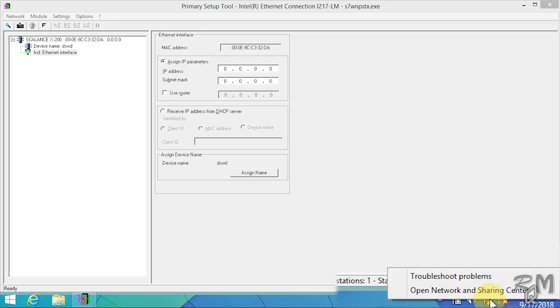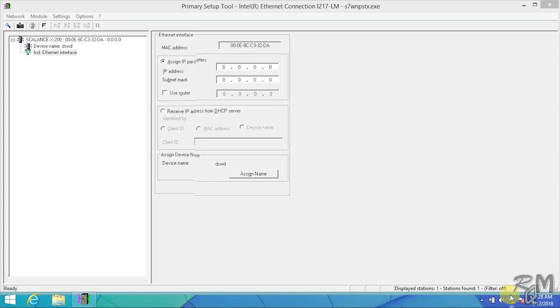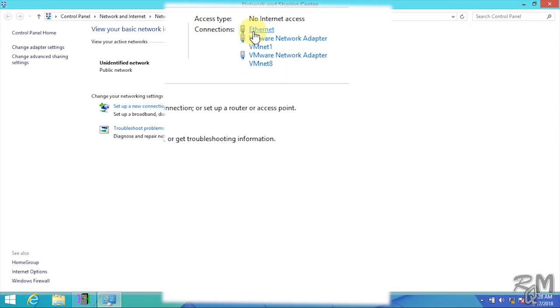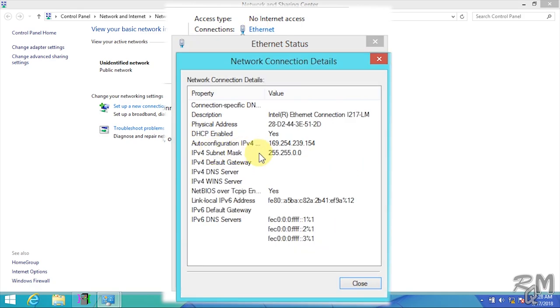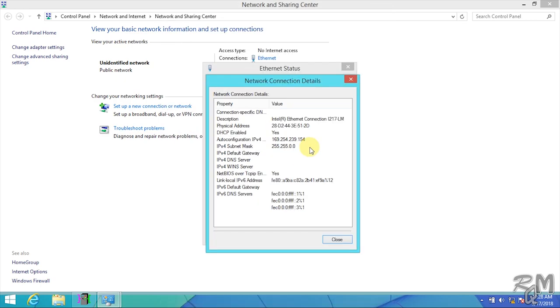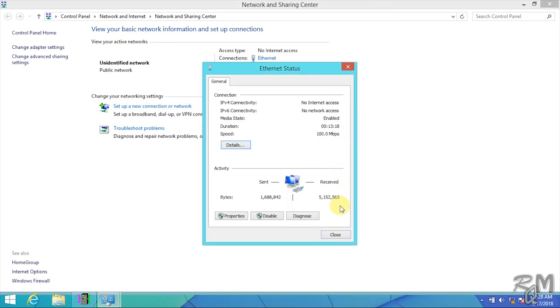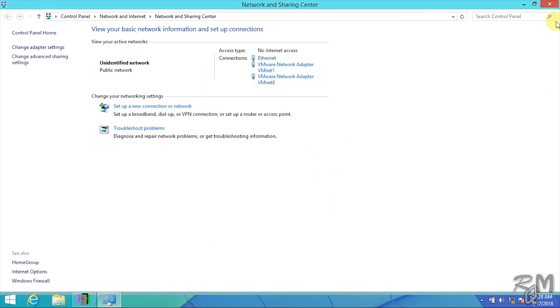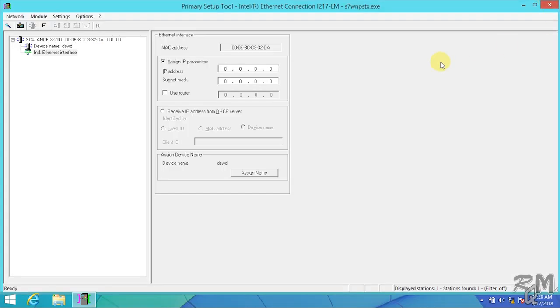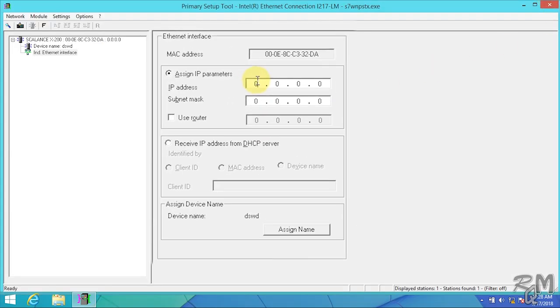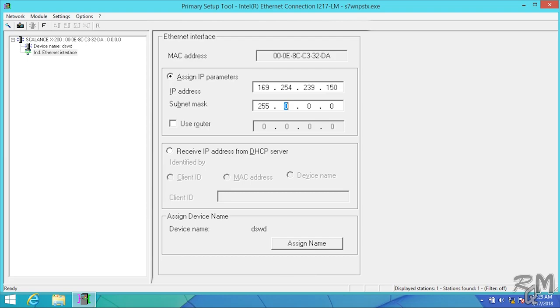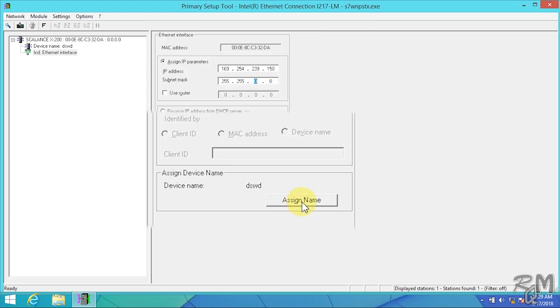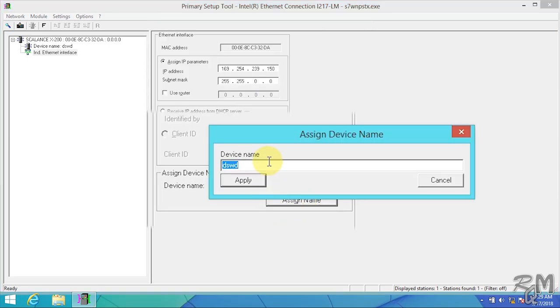Here I am using my laptop so I will assign IP address and subnet mask according to my laptop network settings. Right click on network icon in system tray and click on network and sharing center. Click on ethernet and then click on details button. Here you can see subnet mask and range of IP address of your laptop. Close network property box and network and sharing center. Come back to Primary Setup Tool. Type IP address 169.254.239.150, subnet mask 255.255.0.0.